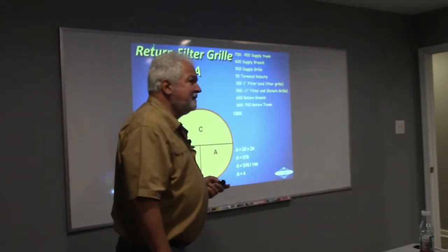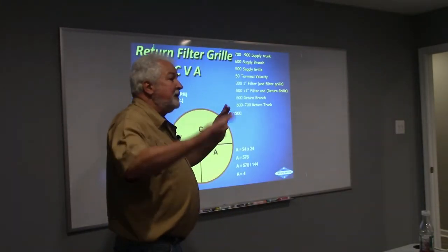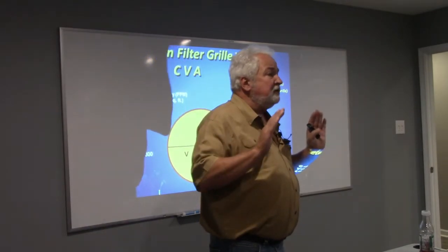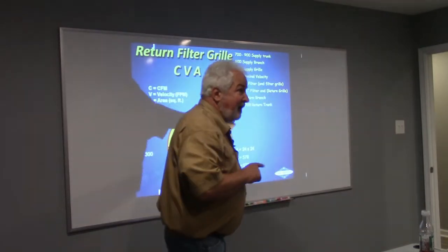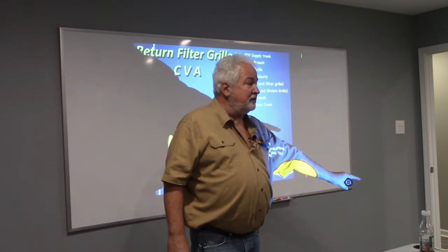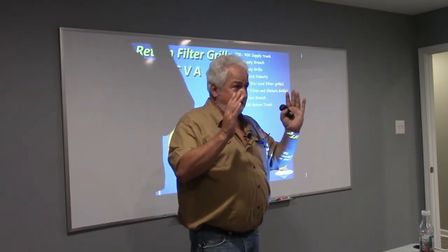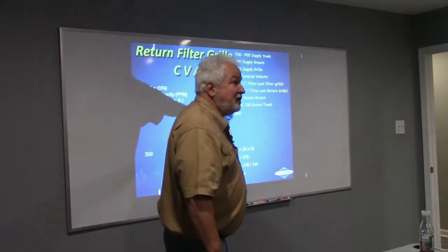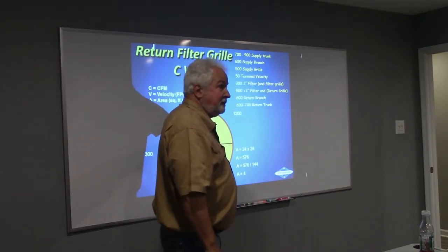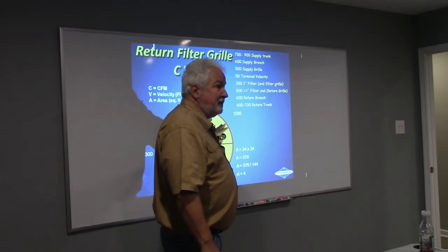The height times the width times 2, things are much simpler. So what I've got to do is figure out how to apply that now to underneath that grille on that door. I've got to apply this to what's going on inside the ductwork. This is how commercial is set up. I've seen them use that calculation. Commercial is completely set up like this.